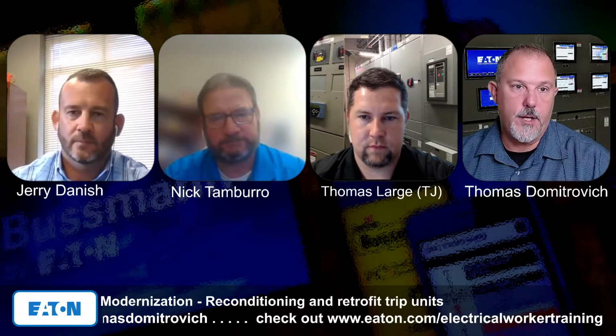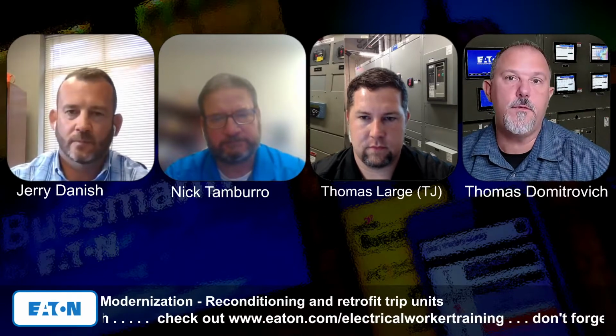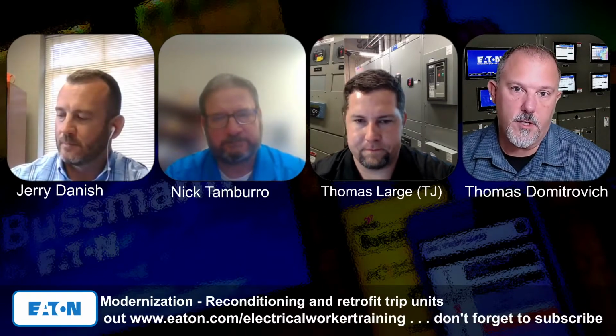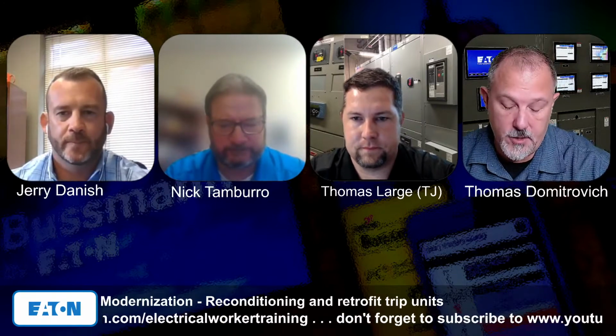Yep. Now that's in Article 100, and then in Article 110, once you meet the definition of reconditioning, what 110 requires is that you put your name on it as the person who's reconditioning it. You have to remove the original listing mark for the circuit breaker, and/or whatever it is that you're reconditioning. And then it's not until you get into Article 240, where we're talking specifically about overcurrent protection, you have 240.88, which deals with circuit breakers, and it tells us reconditioned equipment shall be listed as reconditioned and the original listing mark removed, and it says circuit breakers.